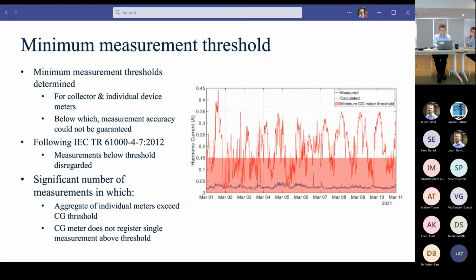Just considering the measurement threshold, we followed the IEC technical report 61000-4-7, in which we were able to identify the minimum threshold for each individual measurement or PQ monitor, and any measurements below that threshold were completely disregarded. It's important to note here that the measurement threshold for the individual generators is different to the measurement threshold for the collector group monitor itself. And so we actually have periods where we have valid measurements for the individual generators, but invalid measurements for the collector group itself. We'll go into a little more detail in a second.